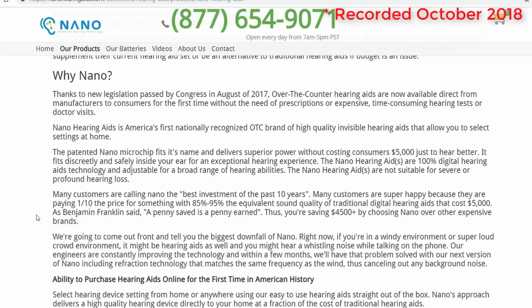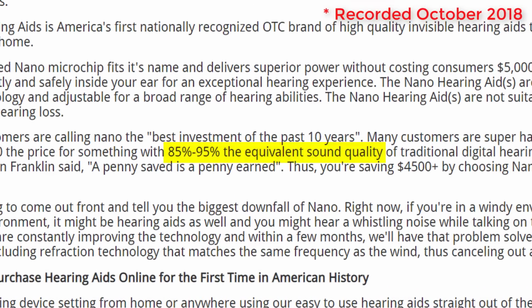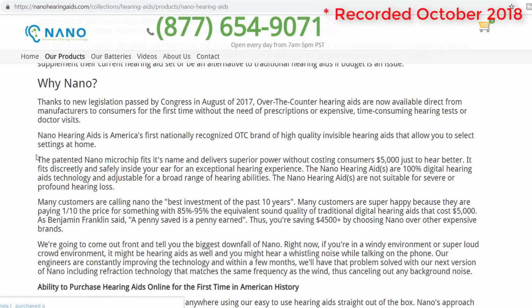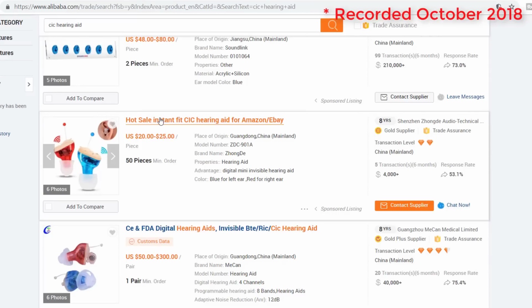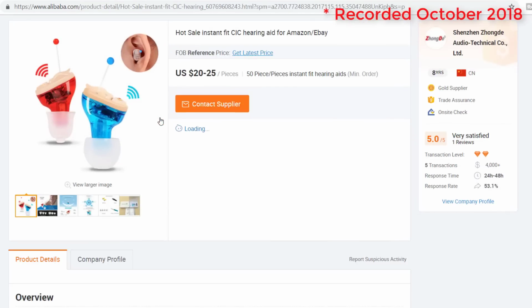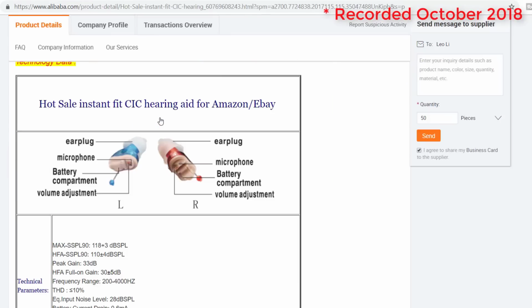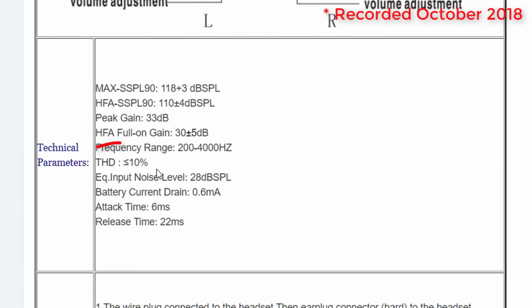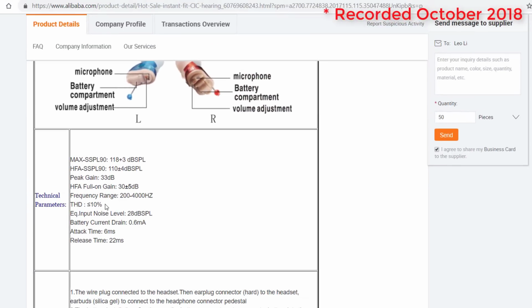Now I want to talk about their statement that they have 85 to 95% the equivalent sound quality of traditional hearing aids. When you actually go look at that Alibaba website, you can see with these particular products what the distortion levels are inside of them. It says you can expect less than or equal to 10% total harmonic distortion, and that number is extremely high. When I get hearing aids into my clinic from a reputable manufacturer, they typically have total harmonic distortion less than or equal to 3%, and oftentimes when I test those products in a test box, I'll get 0% distortion.